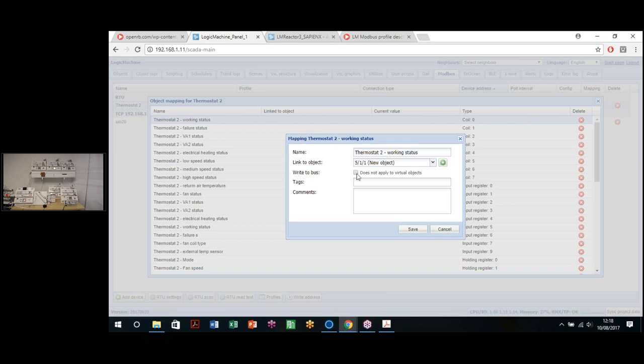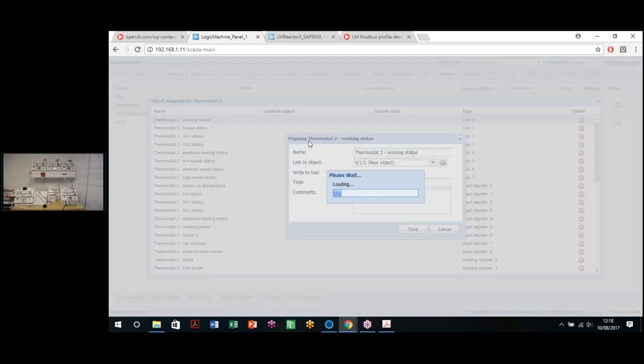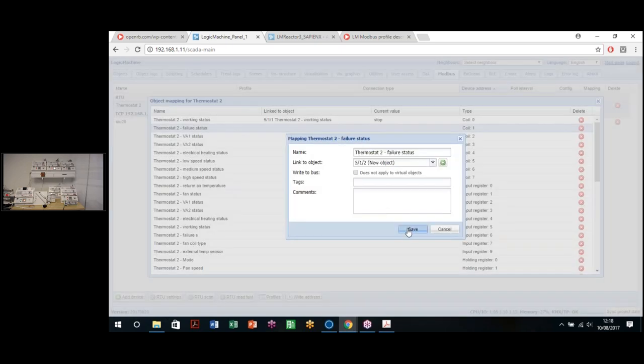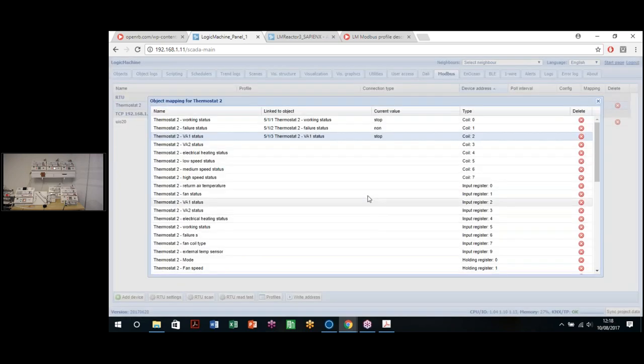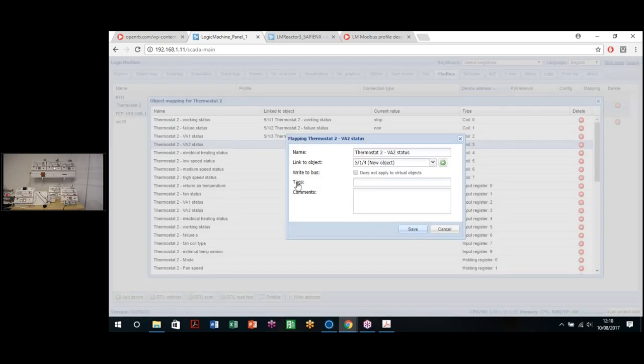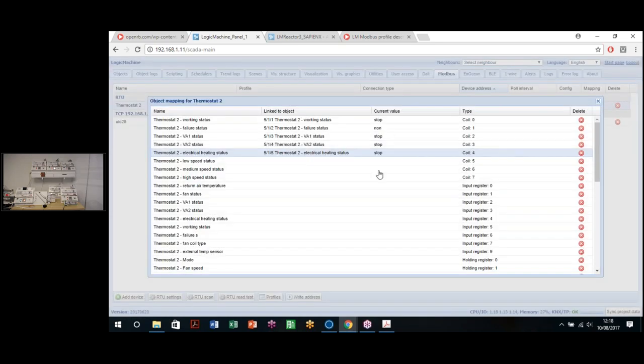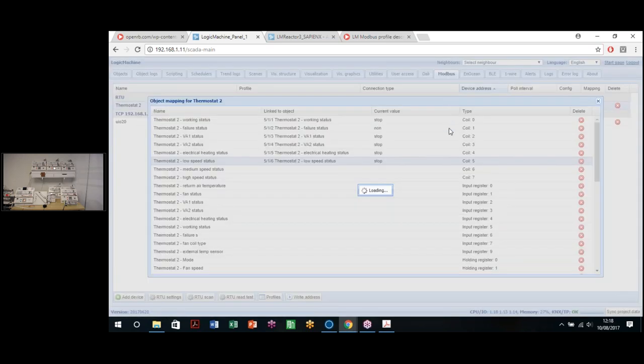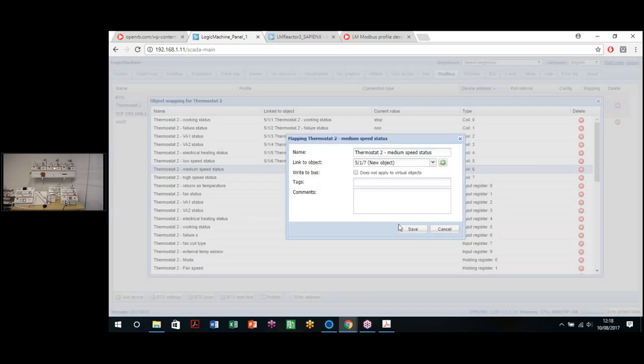We also have an option that asks us if we want to send this information to the bus. If the information is relevant to send to the bus, we can also set this check button. Okay, we click save. And we do this with a few objects, a few registers, so we can see the information is being uploaded. Here we can see that this file is already being filled with the information from the bus. Every 15 seconds, in this case, we will receive information from the bus.